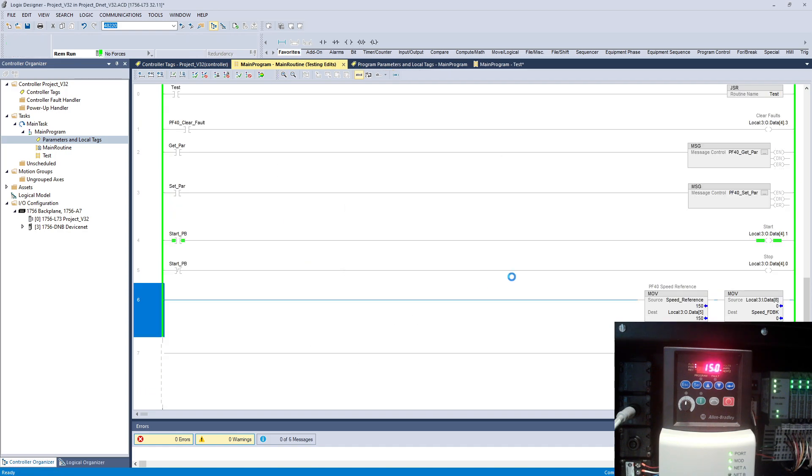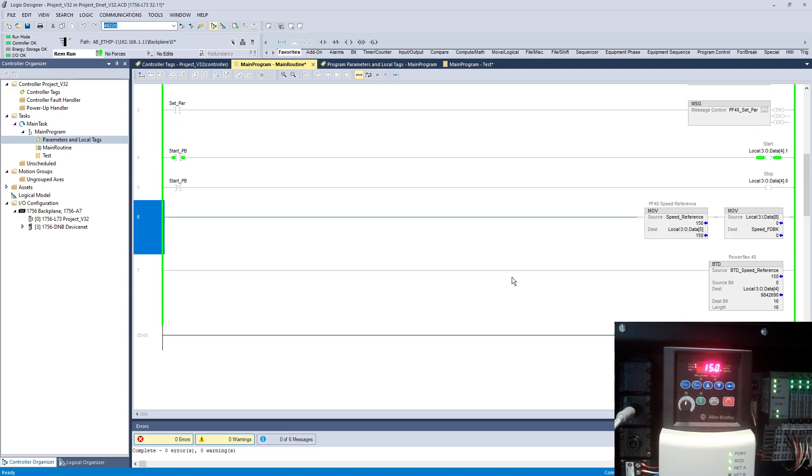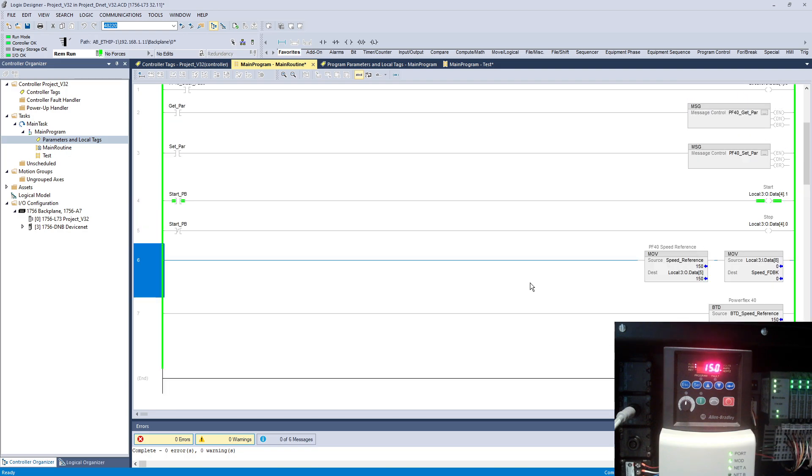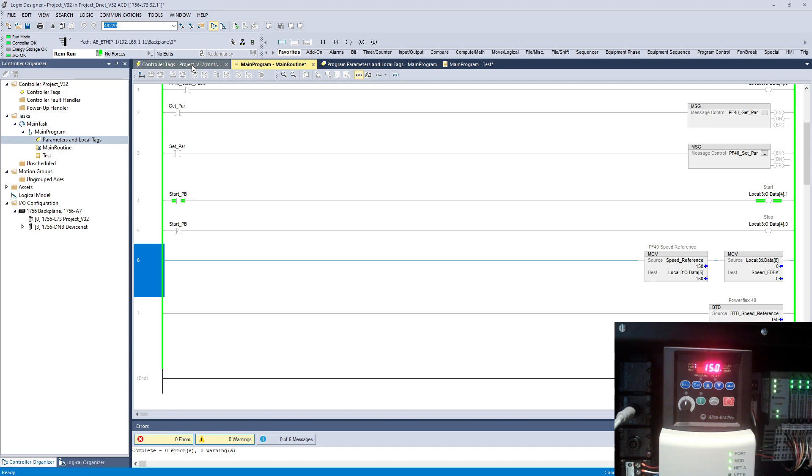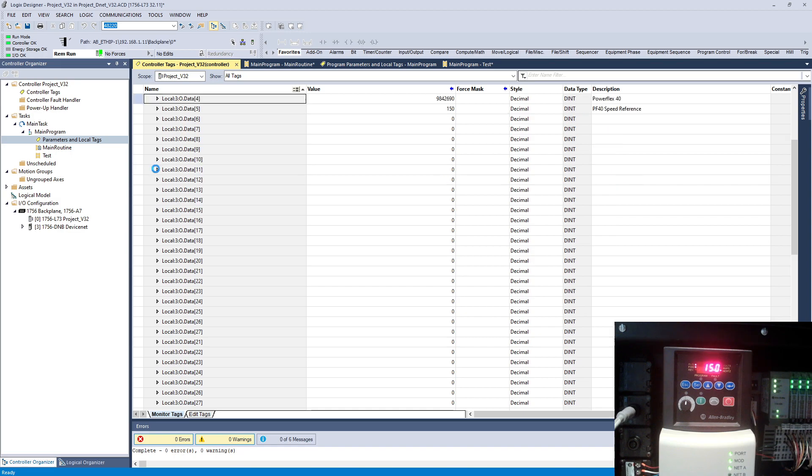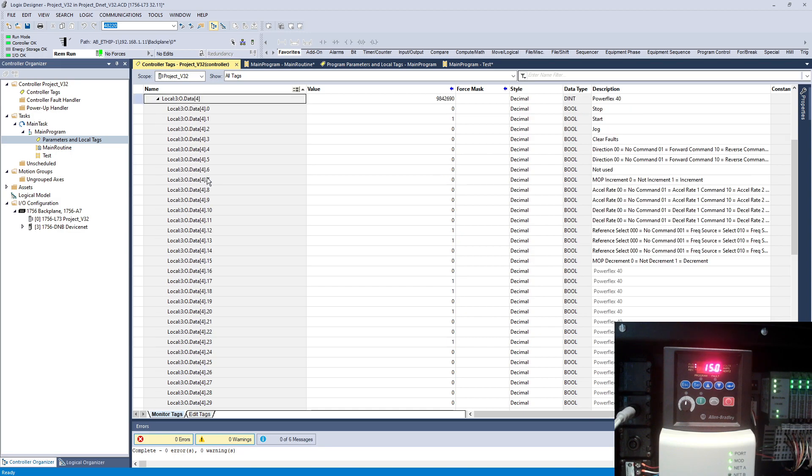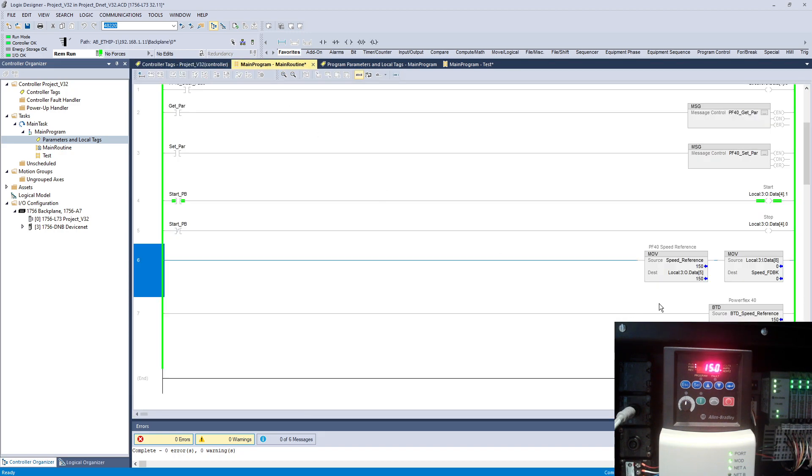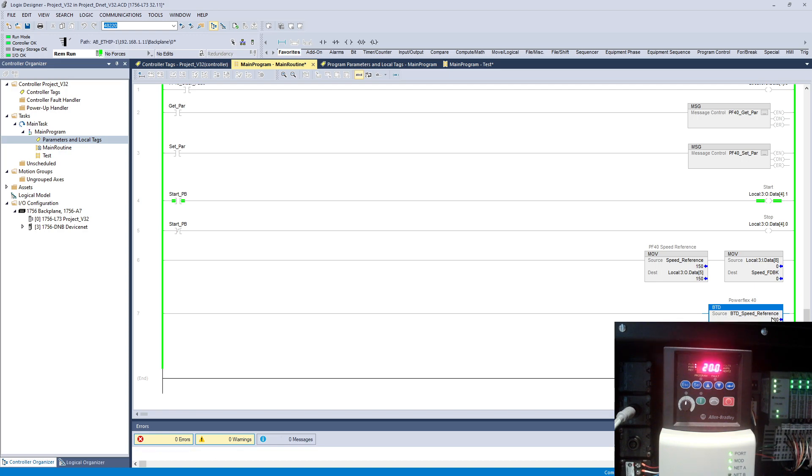Finalize this. That means I'm telling it to start from zero bit of this, and on the local output data number 4 location, which is here my PowerFlex, I'm telling it to start putting those values from bit 16 till all the way 16 length. If I put here let's say 200, you will see VFD speed will change.